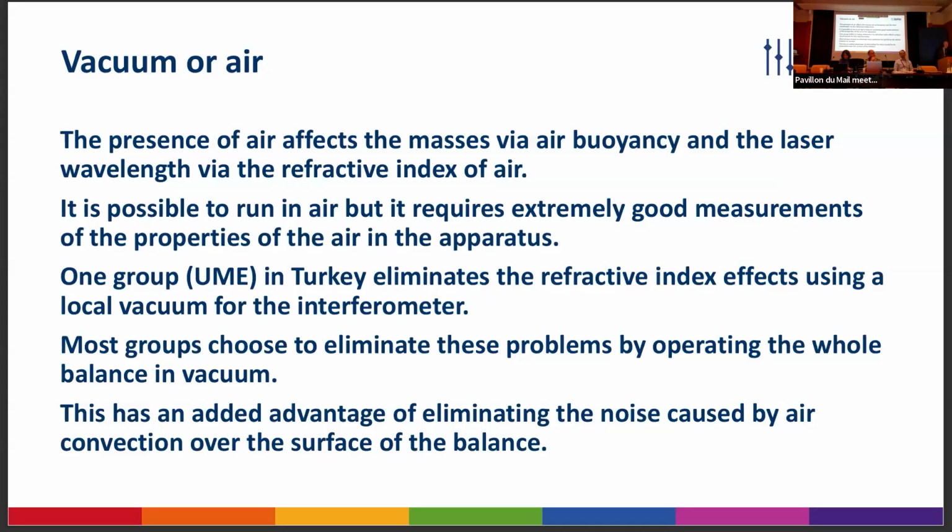Now, vacuum or air: do you run the balance in vacuum? Do you run it in air? If you run it in vacuum, you get rid of air buoyancy, and the laser wavelength is the vacuum wavelength, which is great, but you've got all the problems of working in vacuum. One group, UME in Turkey, have eliminated the refractive index problem using a little local vacuum, and that's a lovely way of doing things.